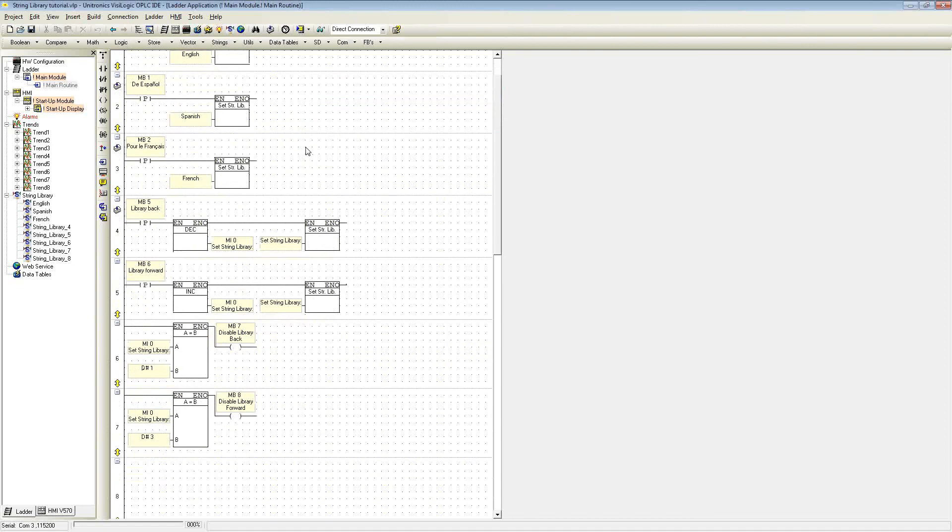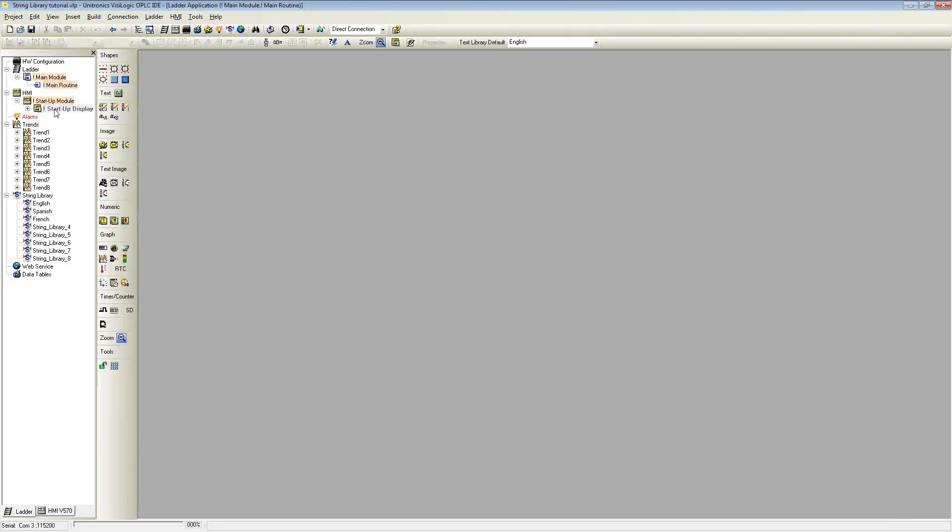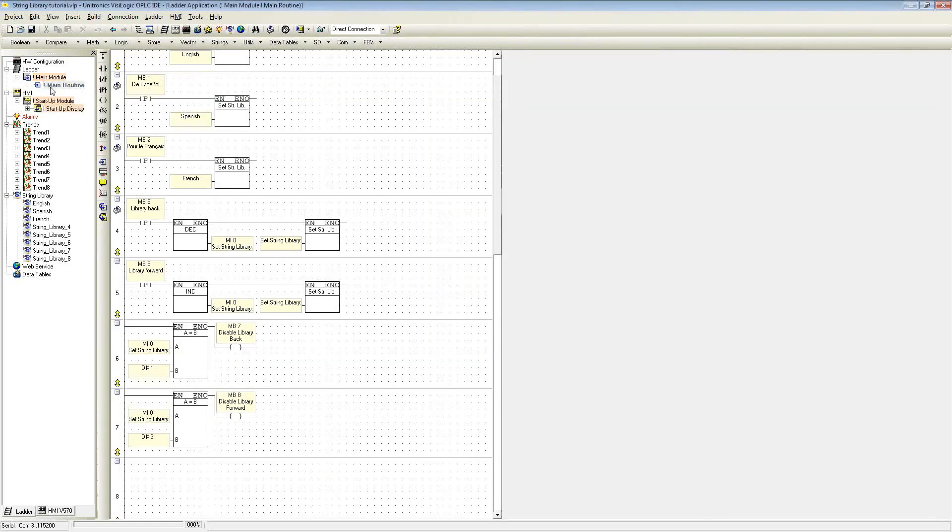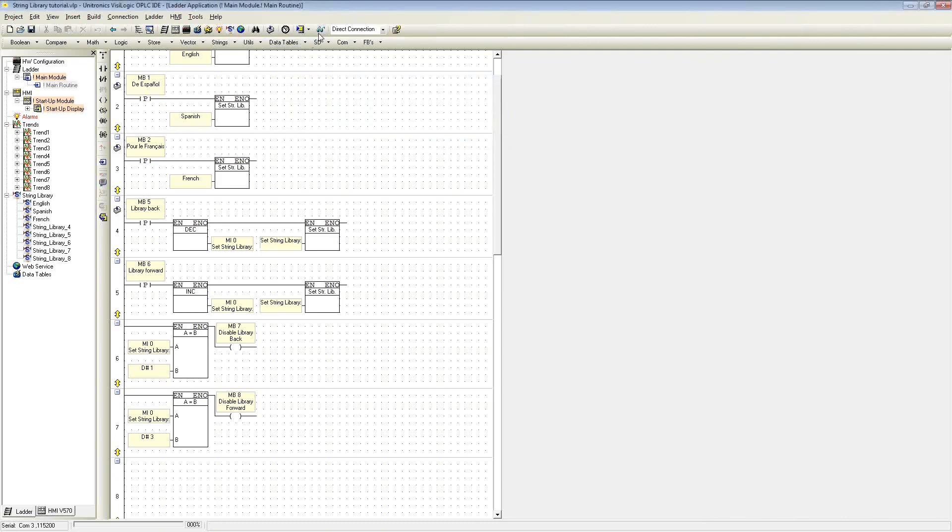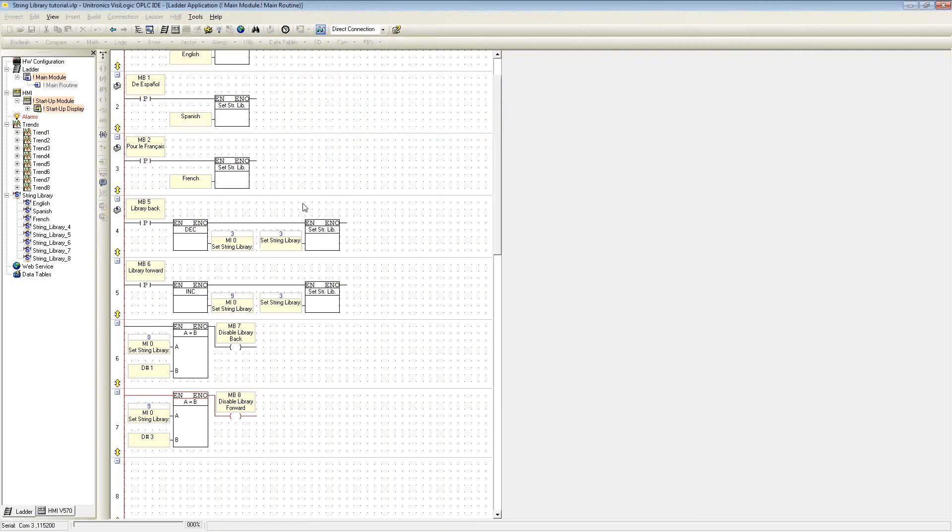I also mentioned that you can indirectly select each library. This is using the other buttons to scroll through left and right of the libraries. Here I have an incrementer and decrementer that uses an MI operand as a pointer. As you can see, when I go online, right now I'm on string library 3. When I press the buttons, it will increment and decrement through the specific string libraries.